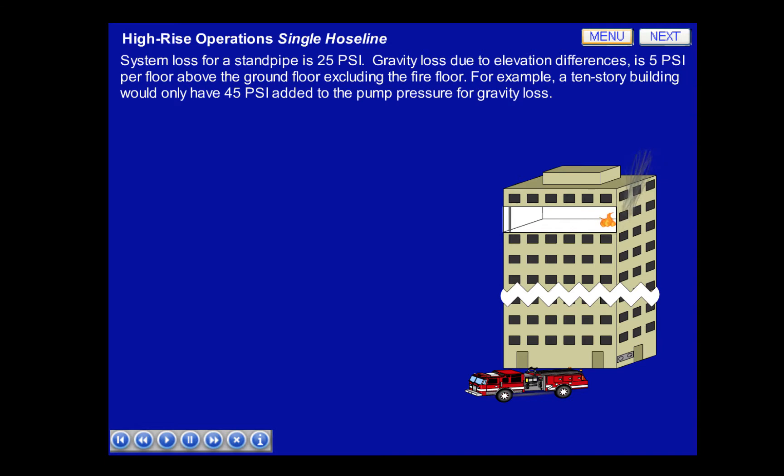System loss for a standpipe is 25 PSI. Gravity loss due to elevation differences is 5 PSI per floor above the ground floor excluding the fire floor. For example, a 10-story building would only have 45 PSI added to the pump pressure for gravity loss.